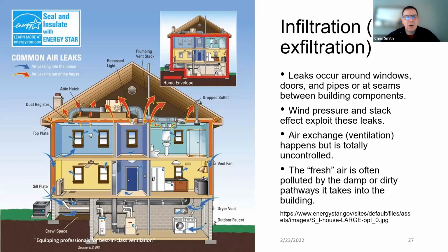Infiltration and exfiltration are pretty common in almost every building. Some buildings are more or less airtight, and so you might have more or less infiltration. But basically, these leaks occur around windows, doors, around pipes or at seams or openings. Oftentimes it's openings in the ceiling plane or the roof where vents or lights are mounted, and the seams between building components, whether it's panels or different building assemblies. These are all places where leaks occur in our buildings. And wind pressure and or stack effect will exploit these leaks.